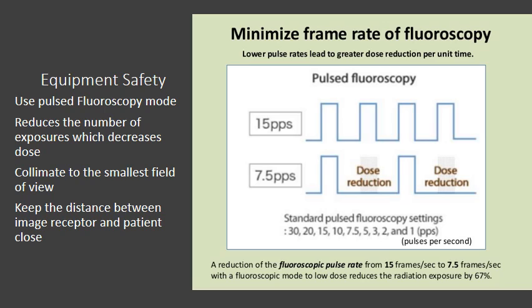So also as a reference, pulse per second and frames per second mean the same thing. So if we keep this in perspective, regular television projects images to us at about 30 pulses per second. There is some equipment where if you reduce your frames per second, it doesn't necessarily yield a proportional reduction in exposure due to some override functions that are designed in by specific manufacturers.